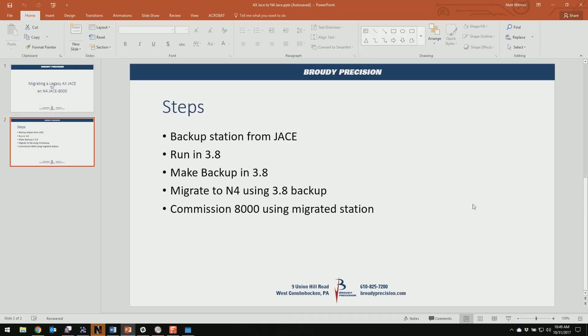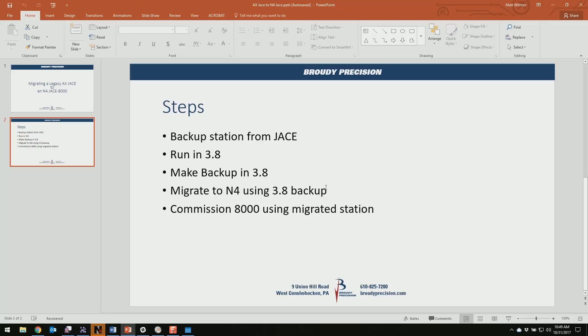So if we go back here and look at our steps, you went from a backup that you took of your legacy Jace, you ran it in 3.8, you made your backup while you were in 3.8. Then you migrated to Niagara 4 using that 3.8 backup, using the console in Niagara 4 and the N4MIG command. And then we commissioned our 8000 using that migrated station. And that's it. Thanks.